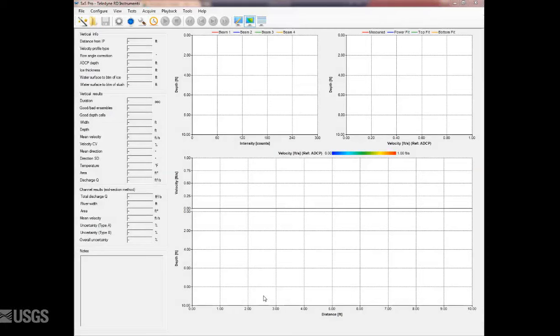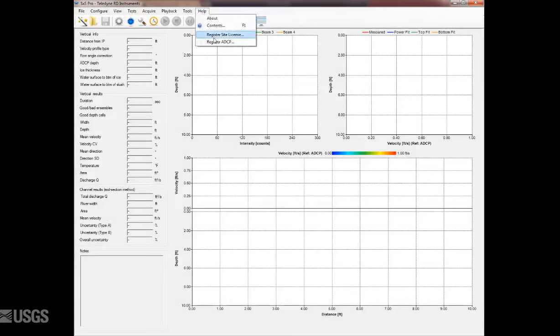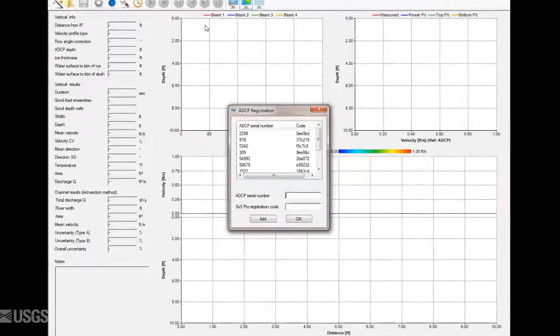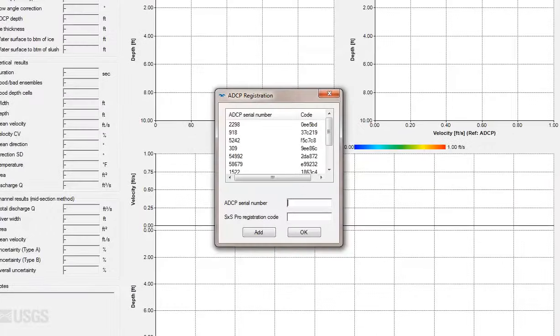Next, you need to enter the serial number specific software key into each computer you plan to collect data using that ADCP. This is done in Section by Section Pro by selecting Help and Register ADCP. You can see I already have several ADCPs activated on my computer. To activate another, simply enter the ADCP serial number, the code you received, and click Add.